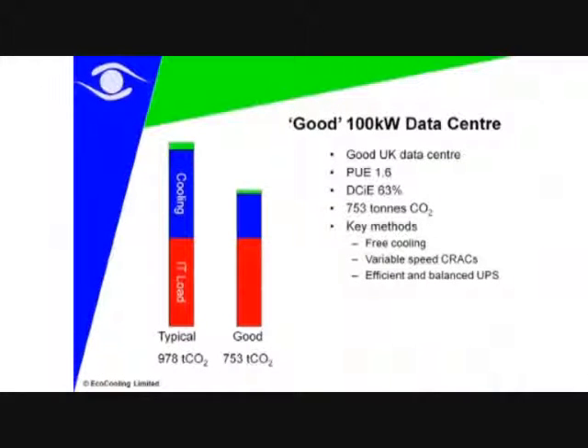So if you look at your 100 kilowatt data center, typical thing, you'll have 100 kilowatt going into your IT load, maybe 100 kilowatts going into your cooling system, and 8 kilowatts into things like UPS losses and distribution losses and transformers. Good data center, like M247, running at about 1.6, but still probably 50% equivalent of their IT load going into their cooling system, using good quality CRACs. Now, what I mean by a CRAC is a computer room air conditioner, your Airedale, Denko, that type of piece of equipment. Using good quality equipment with all of the extras to maximize the efficiency. However, that's still quite a cost load and quite a significant carbon impact.